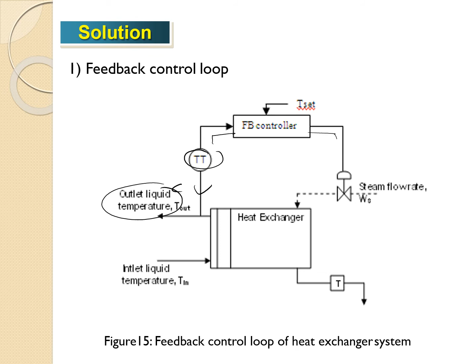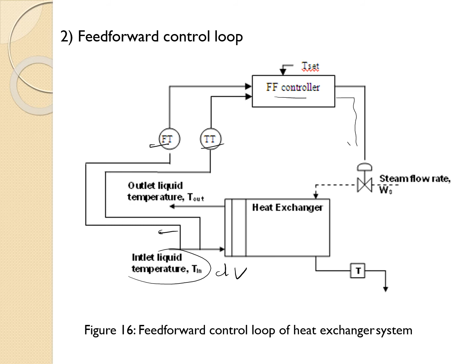So feed forward, we have the other variables, for example inlet liquid temperature. Okay, this inlet liquid temperature would be our variable. Basically, in the inlet stream we also have a flow rate variable, right? That means we have inlet liquid flow rate, and also inlet liquid temperature. So these two variables can be our disturbance. These two variables are measured. Inlet flow rate is measured by a flow rate transmitter, and inlet temperature would be measured by a temperature transmitter, and it will send to the feed forward controller, and it will ask the steam valve to regulate the steam flow rate.